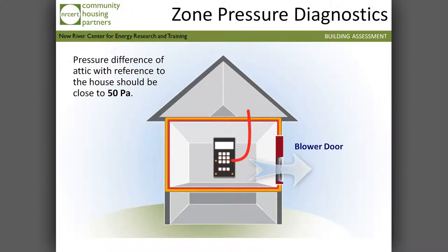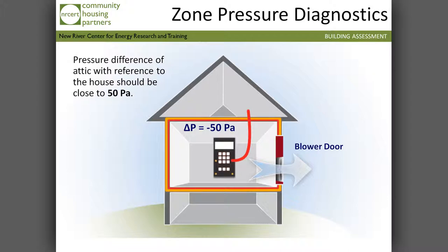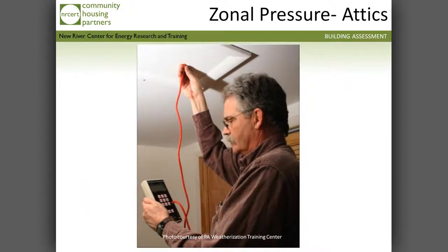Here's the test going into the attic. What number should we see here? 50, if it's tight — don't worry about it being negative or positive, it just depends on where you put that hose. Here's a sample of doing a test to the attic.